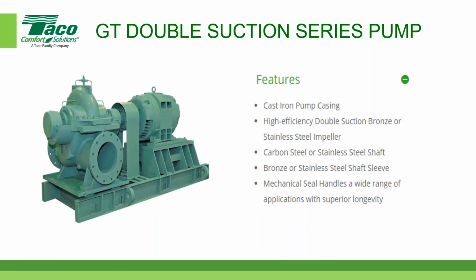Pretty much the same, right? They look very, very similar. Cast iron again - HVAC hydronic pumps are virtually all cast iron, well, 80-90% of them for most manufacturers. But there's that split case again, you can see it cuts away across here, and you've got that rotation issue again.